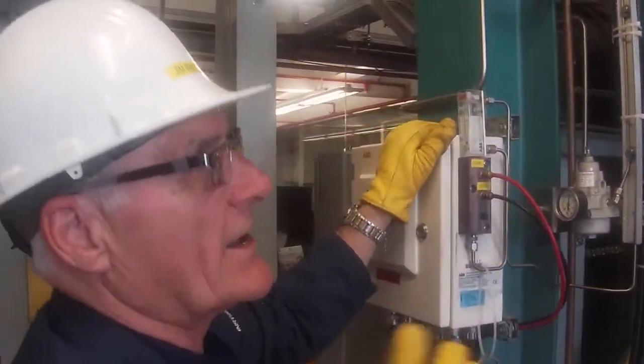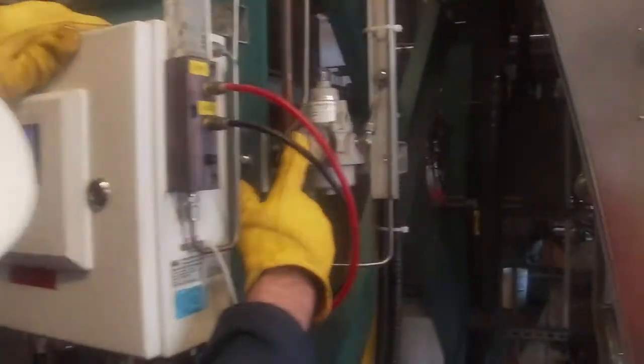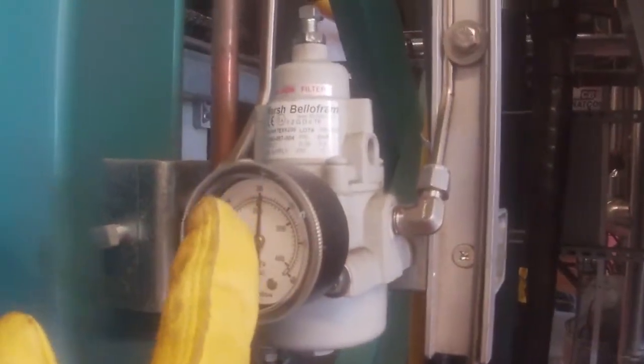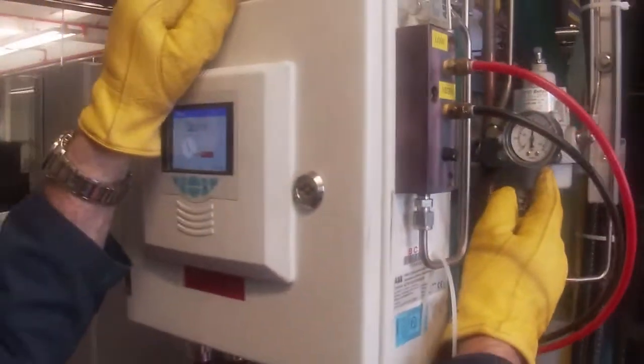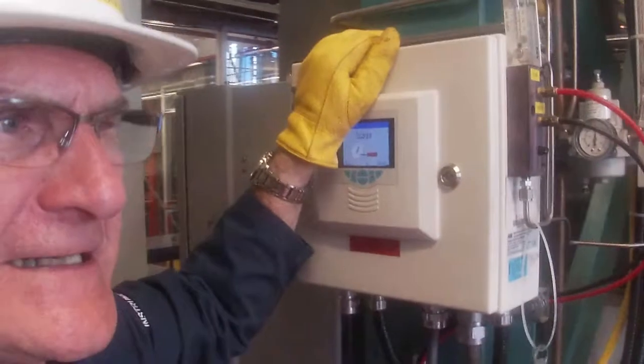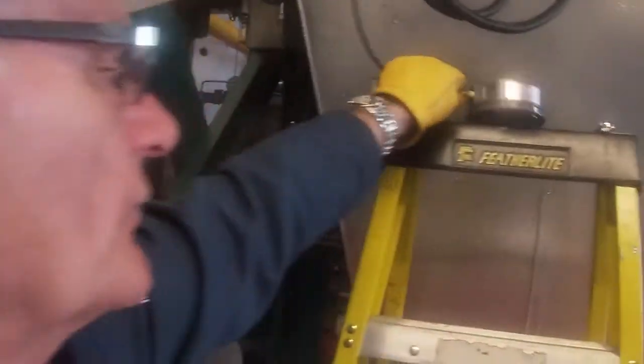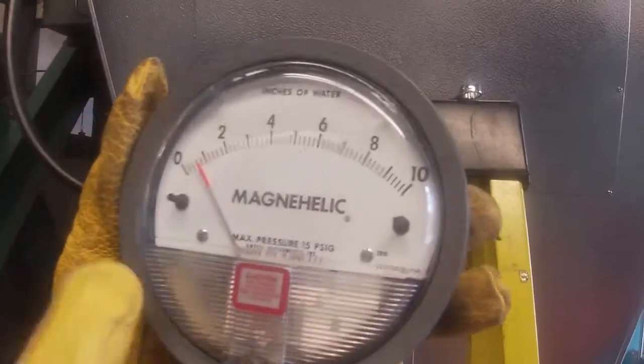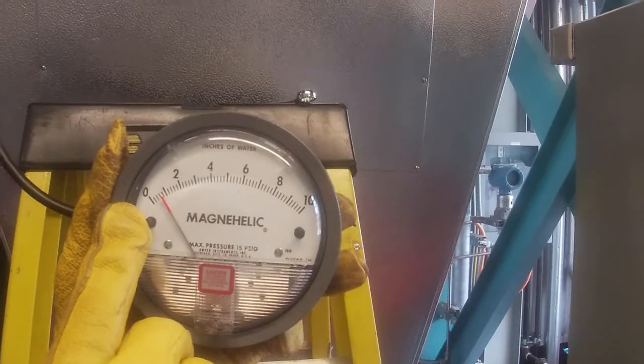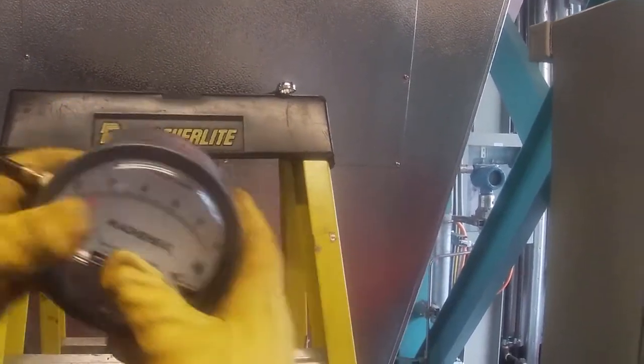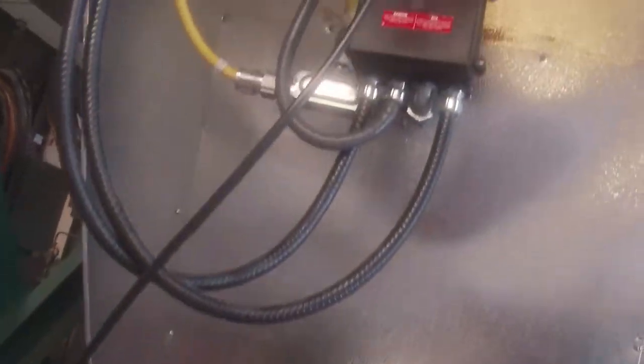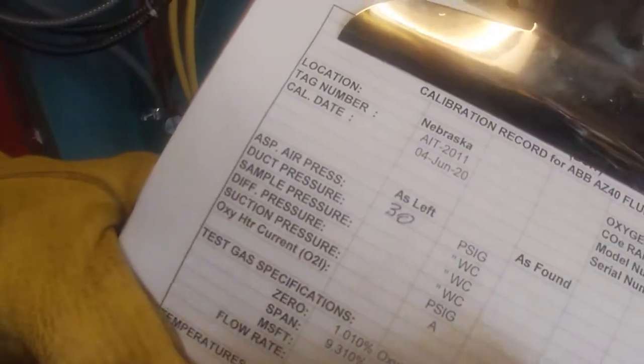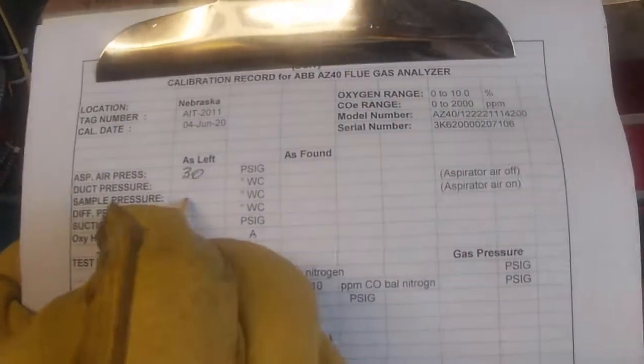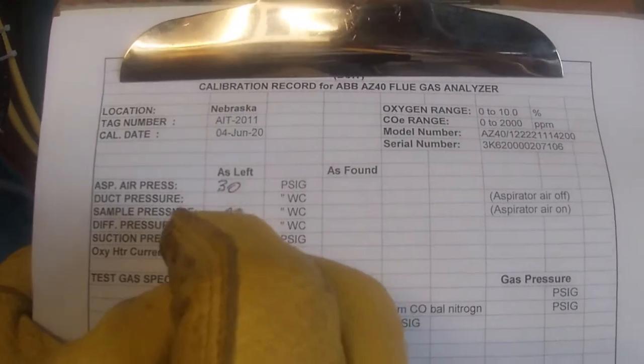Okay. First thing we want to do is measure the air supply pressure. Typically it should be about 30 psi, and right now you can see it's pretty well at 30, as accurate as one of these gauges is going to be. Right now we're aspirating samples from the boiler through. I've got a draft gauge here, and it's measuring that the draft is sitting at minus 0.7 inches of water column. So I'm going to write that down on my spreadsheet. The air supply was sitting at 30 psi. Duct pressure, this is with the sample pressure, was at minus 0.7, I think. Yeah, minus 0.7.